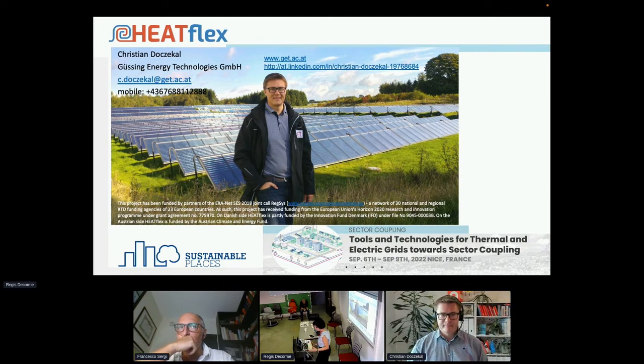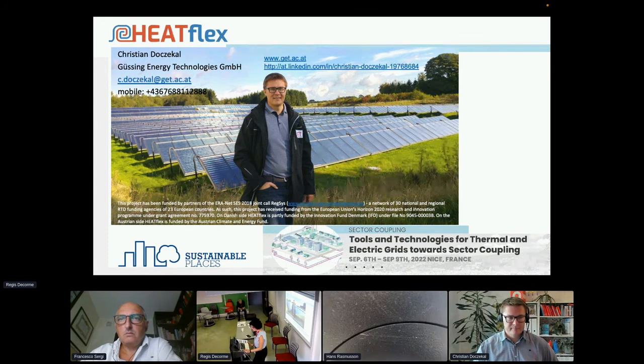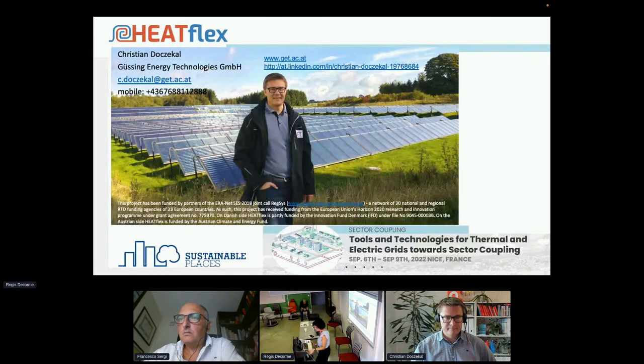If you have a high temperature grid, you can use the heat from your grid in summer also to produce cooling, giving the system an extra mode of operation in times when there's usually no heat demand in residential districts. You can charge the storage when you have excess heat or when grid heat is cheaper, reducing overall heating and cooling costs, since being a weekly to monthly storage, even in winter you can store heat when it's cheaper and use it later for residential or industrial applications if temperature levels allow.